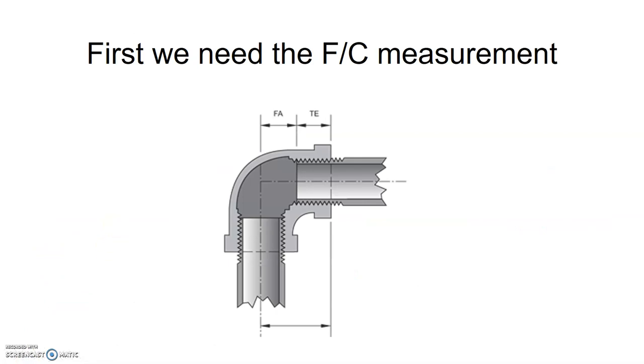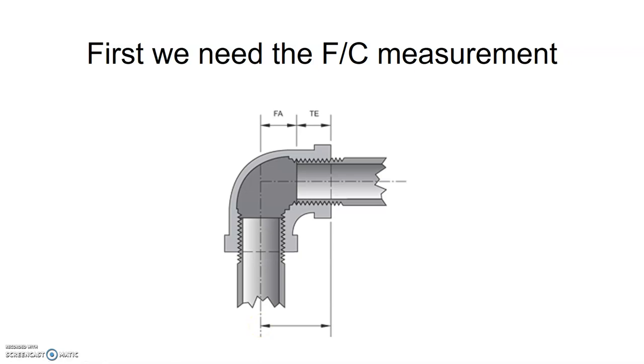The first thing when we're trying to determine the FA is we need to know the face to center measurement. We need to know it by either measuring the fitting ourselves, getting our measuring tape right on the face of the fitting and measuring over to the centerline of the fitting on the other outlet side, or we can get it off a manufacturer's table. Sometimes a manufacturer's table will provide us with our face to center measurement, and it all depends on the size and type of fitting that we're using, because it will vary from 90 to 45 to T to other types of fittings and other types of nominal pipe size.